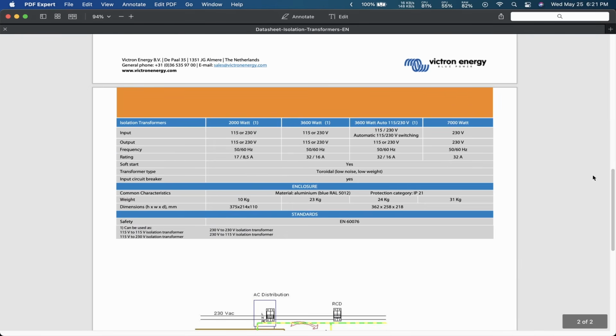The big drawback of this setup is that isolation transformers do not change the frequency, only the voltage. So if you have AC powered equipment that you want to use that simply won't work on the wrong frequency, you'll need to do a little extra thinking.